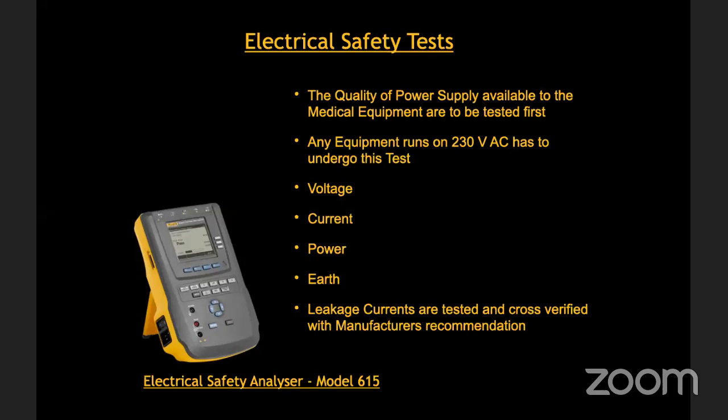Then it tells about the voltage, current, power, earth leakage current, touch current, chassis current. The person using the machine also should not get a shock.